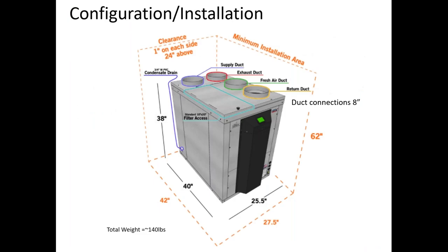In the configuration of the system, the ducts all come out of the top of the unit. It's much like a conventional ERV or HRV. There are four duct connections, two running to the outside, the fresh air intake and an exhaust to the outside. And then there are the ducts that run into the house. So the return duct pulls air from exhaust locations, and then a supply duct feeds air into the house. A condensate drain can run either to a floor drain or a condensate pump. And then the system has this vertical orientation. And you can build a platform to have it higher off the ground if you like as well.